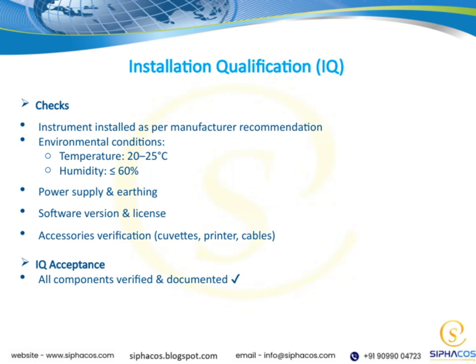Accessories are also checked at this stage, things like cuvettes, the printer, and cables, to confirm everything is present and in good condition. When all these checks are completed, we move to the IQ acceptance phase, where we verify and document that all components are in place and functioning correctly. This documentation is key to maintaining a clear record of the installation process, confirming that everything meets the required standards. In summary, these steps help us lay a solid foundation for reliable, accurate results throughout the instrument's life cycle.